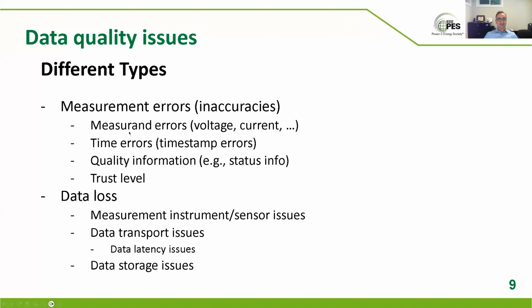Maybe your CT has an error, maybe your relay has an error. So you've got basically measurement error, what you're trying to measure, voltage and current. In synchronized measurement, you could also have time error. The time tag you're putting on it could be wrong. And then often enough there could be quality information, like synchrophasors have a quality status bit, and that could have some wrong things in it, or could be right. Overall, together, all of those give you a trust level in the measurement quality. And there's a lot of metrology effort to get these right, and it's super important.